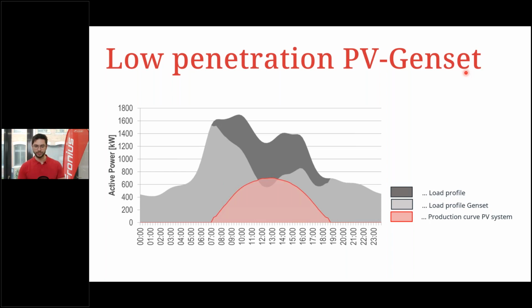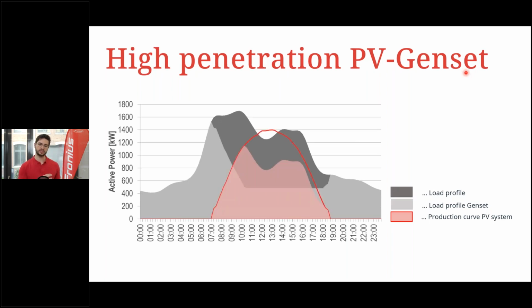As I mentioned, in a low penetration system, compared to the load, we have a very small PV generator on the roof. So low penetration does not need any controlling at all. And then in comparison to that, there is the high penetration PV genset solution where, as the name already indicates, we have a very big generator on the roof. And at some point, we might have a lot of surplus energy, even more than we have load to supply. So in this case, we then have to control the output of the inverters so that the diesel generator can run at the minimum load. This we can see here.